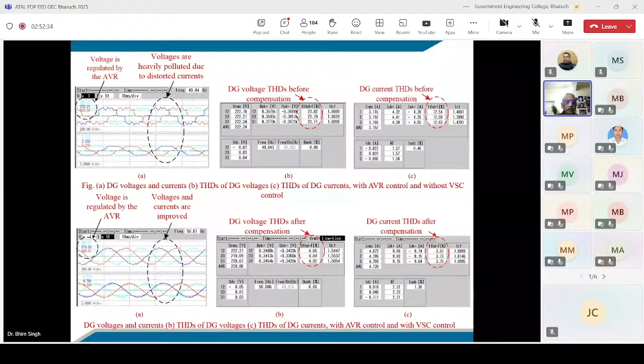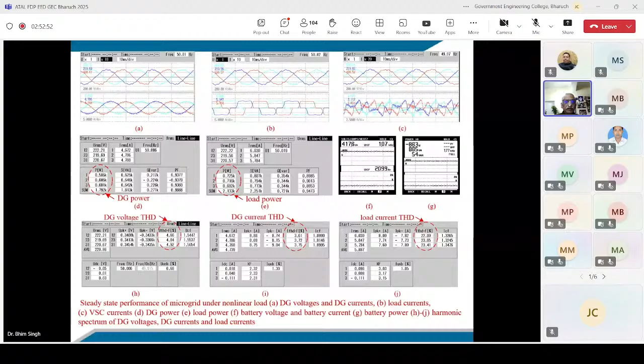We are able to operate successfully without much problem. You can see without compensation how the DG set feeds the non-linear load, and with the converter switched on, it is able to reduce the voltage THD to less than 5%. It was very interesting what we looked into experimentally. We earlier did a lot of work with simulation, but this we worked out experimentally also, for solar generation variation and sudden load change, and how they affect the system. But you can see the terminal voltage is not affected at all, with voltage and frequency, and these are all control instruments.